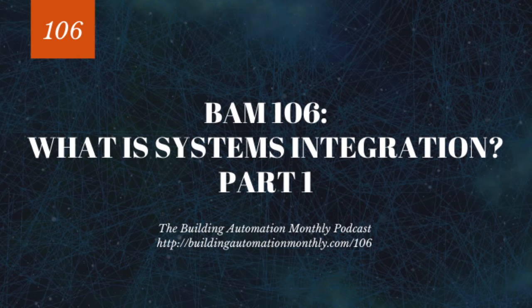The second thing is that you have to understand where you are with the protocol. I often find folks using field level protocols, meaning stuff at the field bus, field controllers, serial protocols. So think stuff downstream from the supervisory device. Then they're trying to integrate those to network layer protocols. They say, I've got BACnet MSTP and I'm going to tie it into BACnet IP, and they expect the rules to be the same, but they're not the same. So you really have to understand that.